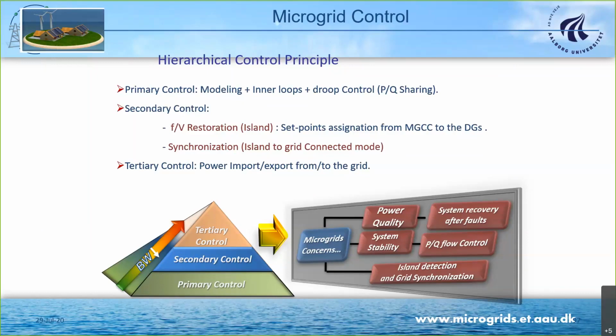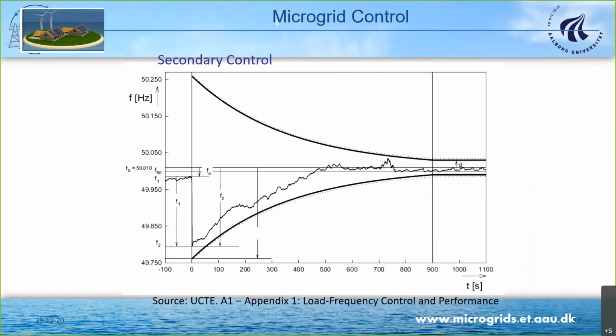The next level is the secondary control, which restores the frequency and voltage deviations produced by those droop controllers, and also handles synchronization. Finally, the tertiary control in our microgrid system is the energy management system, used to optimize the whole grid.